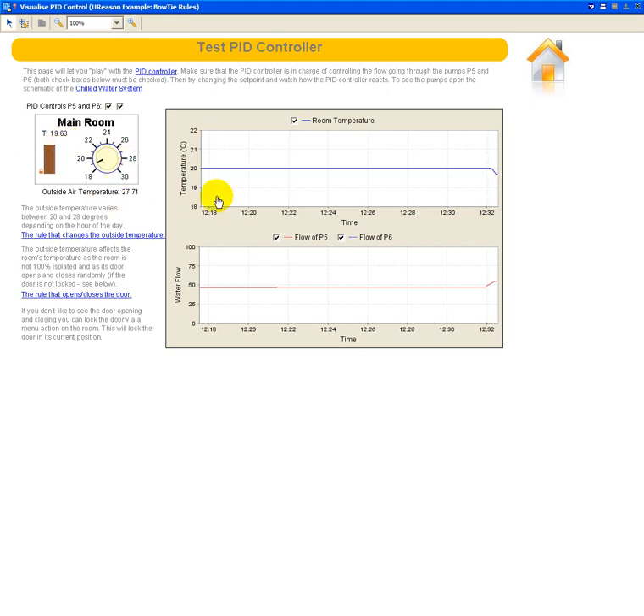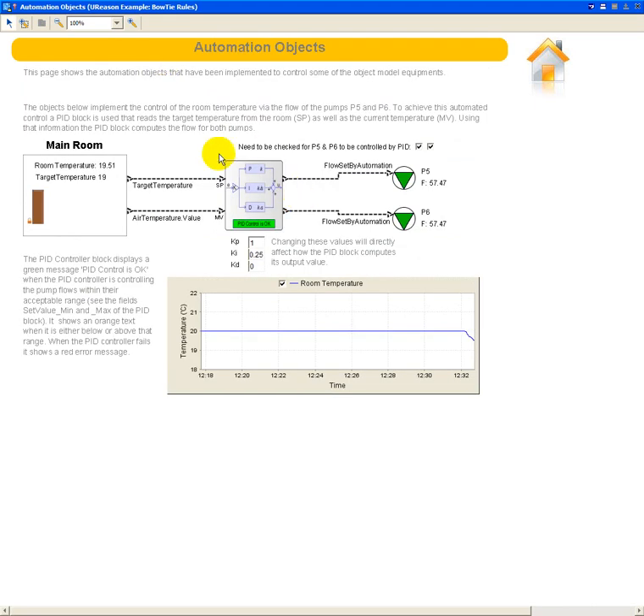This is done by a PID control. We can make the life of this PID controller, or I can first show you the PID controller here. The PID controller is a little object like this that takes its value, its set point, and its temperature value from an object like this through connections that are strip line here, and it implements a PID logic, obviously, and the result of these calculations are actually sent inside the flow of both P5 and P6, and we see now that the temperature is slowly going to adjust itself around the 19 degrees.